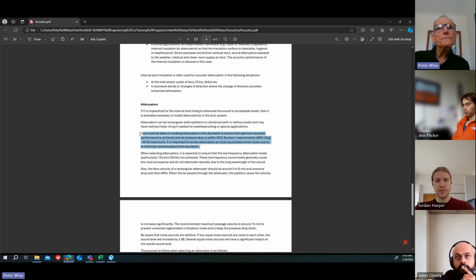Now, we need to take care in locating the attenuators in the ductwork to ensure that optimum acoustic performance is achieved and the air pressure drop is within NCC Section J requirements. Where we locate the attenuator doesn't necessarily affect the pressure drop through the attenuator. We can select an attenuator for 40 pascals maximum, and that's what we have to do to satisfy the NCC. But the pressure drop through the attenuator will be increased if they're located in a bad location, such as right after a bend or after a branch. Fittings in the ductwork will affect the performance of the attenuator and will affect the pressure drop.